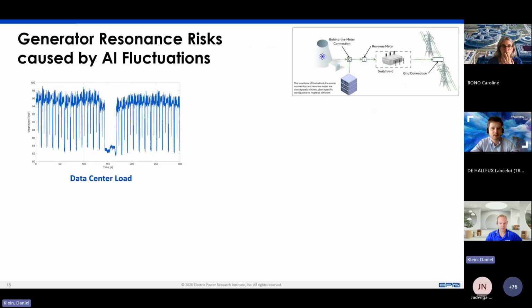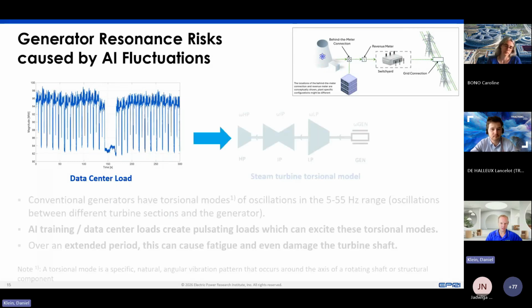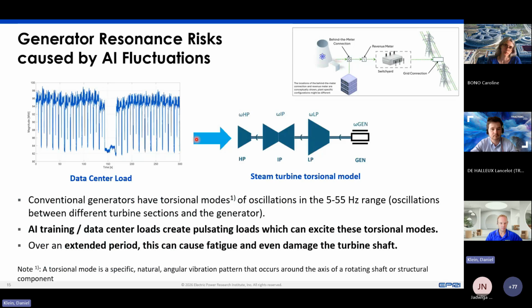As we look at the co-location of a nuclear power plant, that's what you see here on the right side. I have my nuclear power plant providing electricity to the grid. But if I have a data center that is basically behind the meter connected, or even if that would be on a grid but very physically close or next to a nuclear power plant, that fluctuation the data center causes and the electricity demand has an impact on our steam turbine shaft connection.